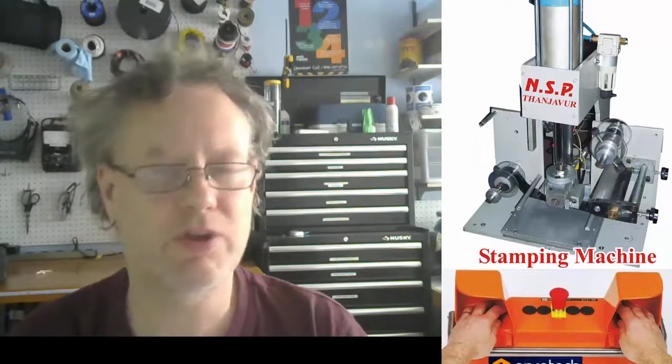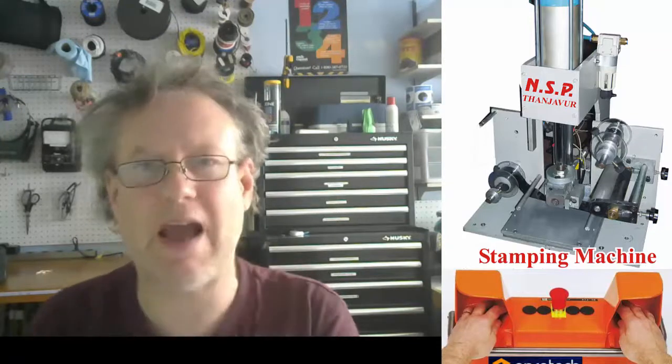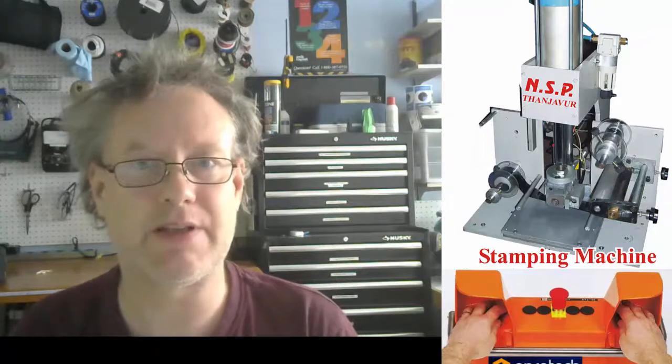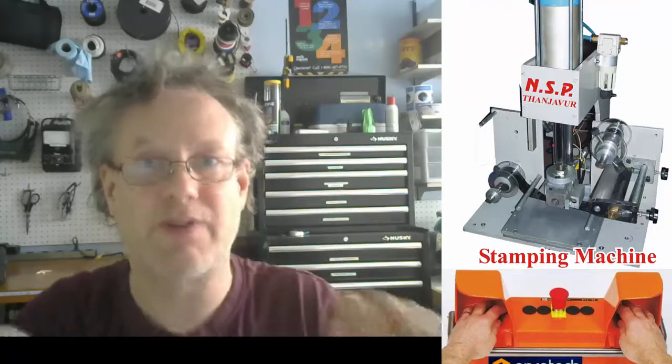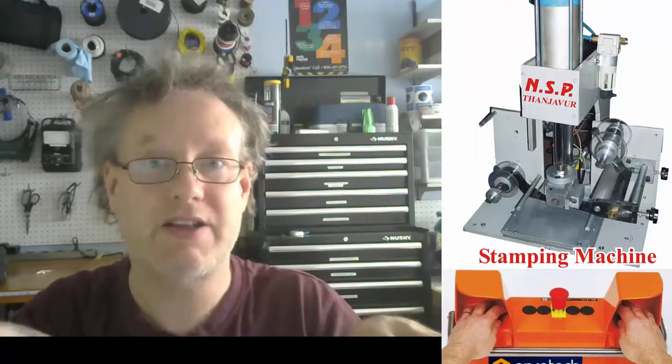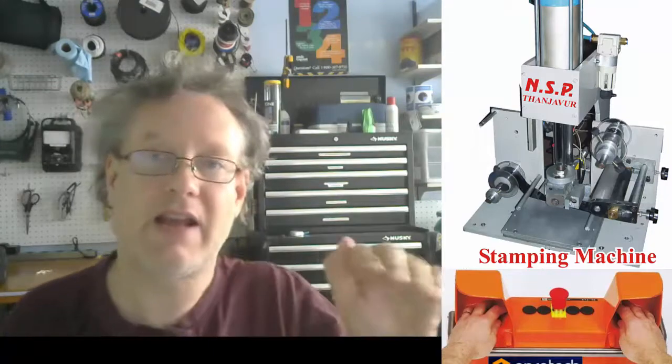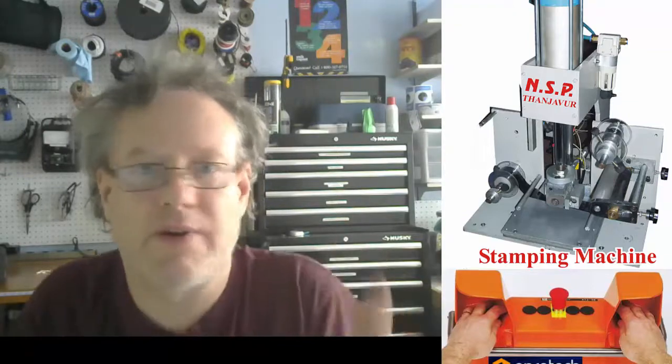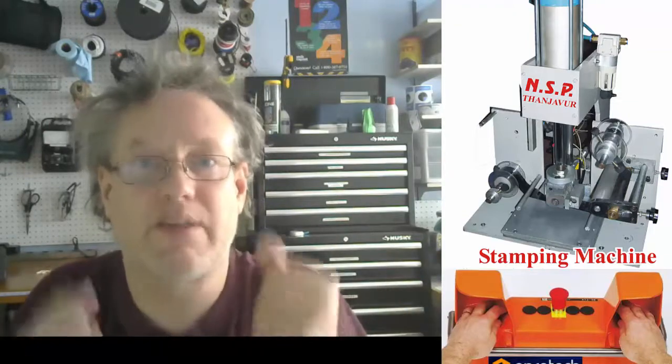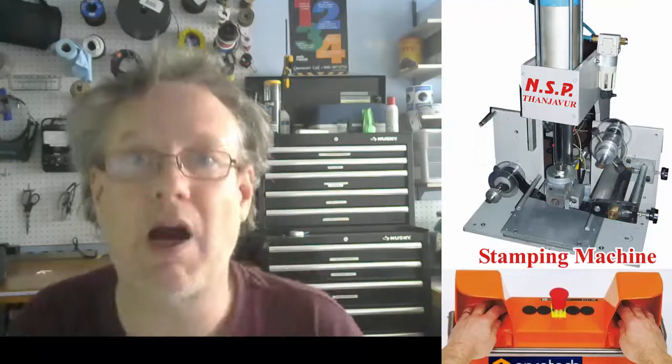Now, there's also something called two hands no tie down, which is pretty cool. That's not part of this lab, but I thought I'll unpack that just for a second. Now that is actually timing. What actually happens is that someone created two hands no tie down because what operators were doing was they were actually tying down one of the buttons. They're actually just taking one of those of the two hands where they put their hands and they're actually putting like tape on and tying down one of the buttons. And then they can actually activate the machine quickly with one hand and it made the process more quick. So they could do their job. They could actually produce more parts.